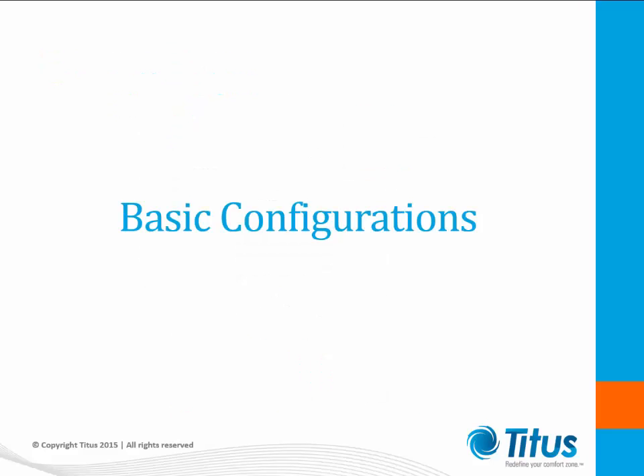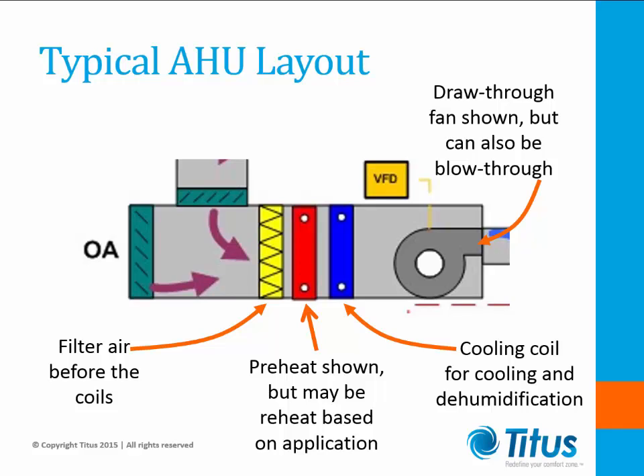Let's take a minute and look over the basic configurations. Just to revisit what an AHU is doing, air is brought into the unit, passing over the filters through a heat transfer configuration and supplied to the building. Many of those configurations use two methods of supplying air, a draw-through or blow-through design.